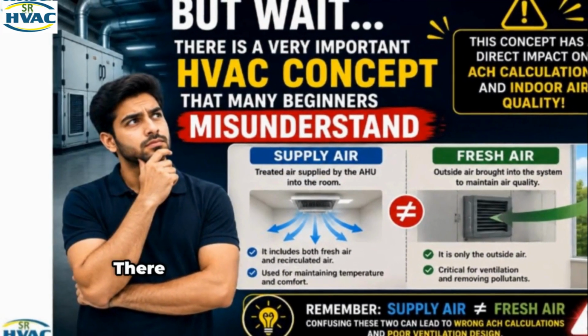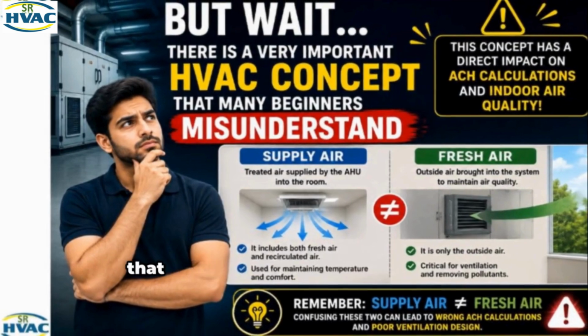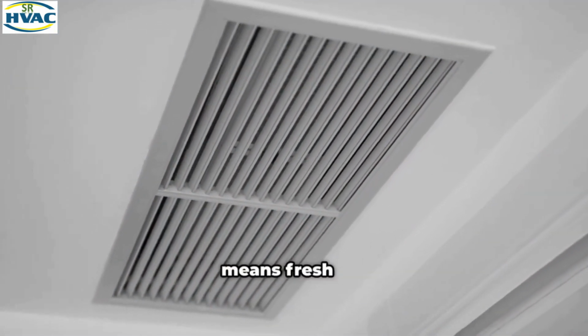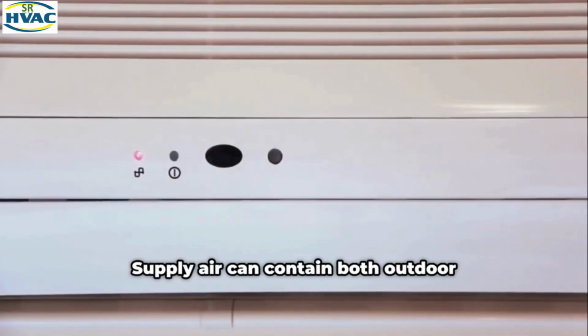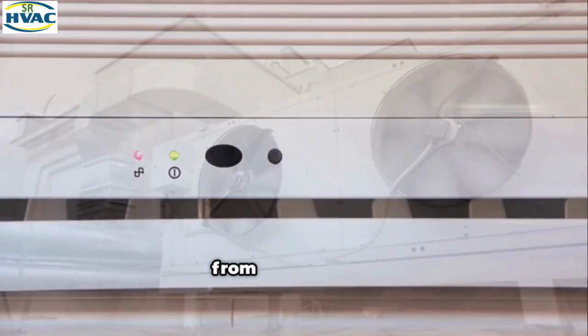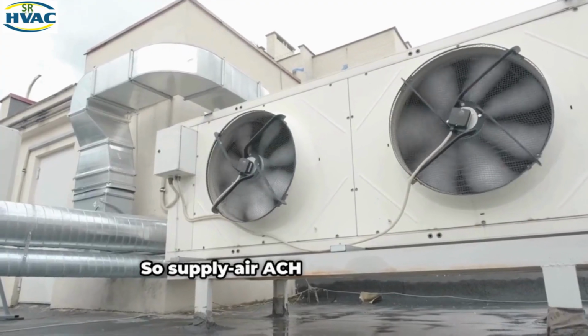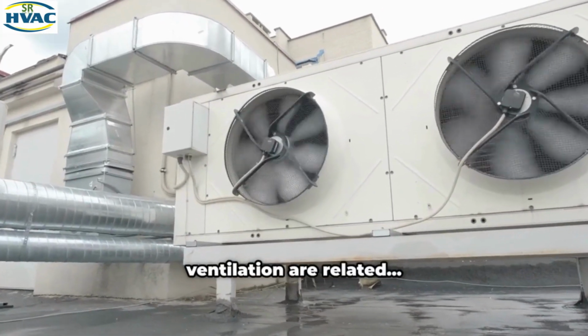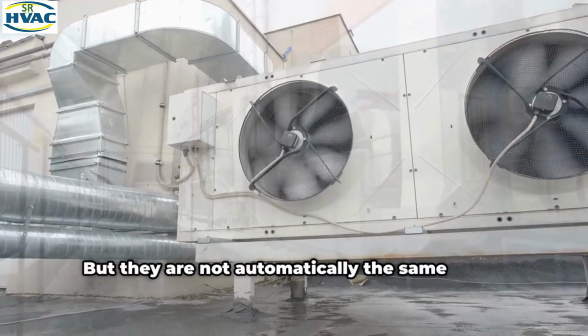But wait, there is a very important HVAC concept that many beginners misunderstand. They often think ACH automatically means fresh air, but that is not necessarily true. Supply air can contain both outdoor fresh air and recirculated return air from the building. So supply air, ACH, and outdoor air ventilation are related, but they are not automatically the same thing.